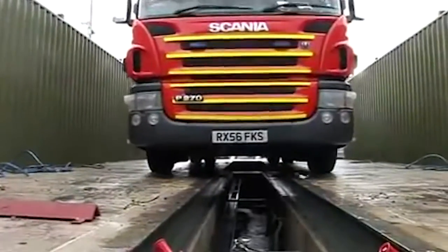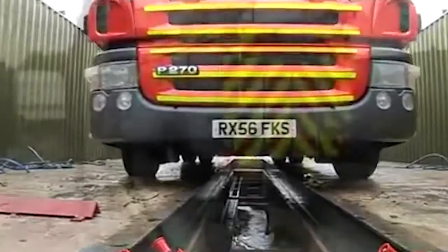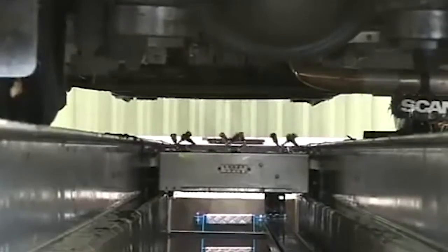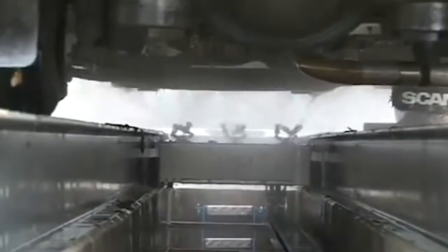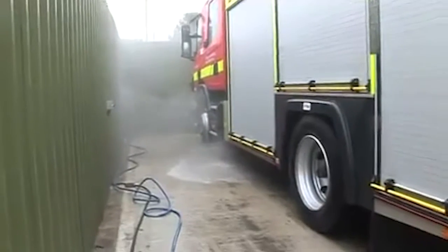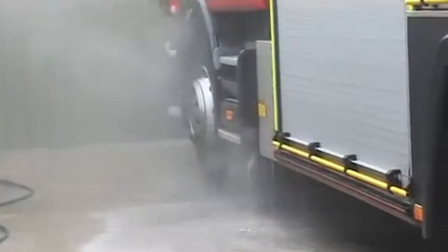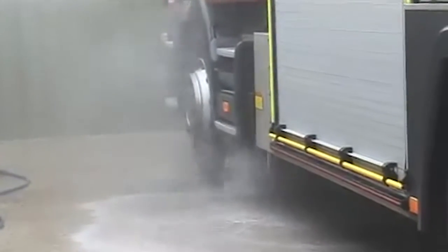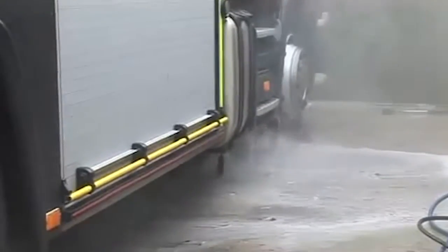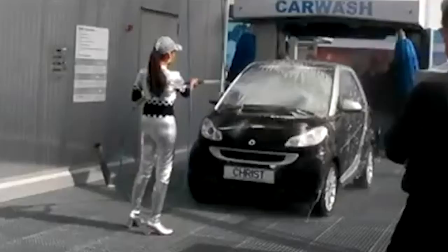The cost of clean water is spiralling, and its abundant supply is not guaranteed in the long term. There are two ways to reduce water usage. One is to increase the spray pressure to achieve the same cleaning effect but using less water. There are still companies that use low pressure, 5 to 10 bar, instead of 40 to 70 bar. The other is to use recycled water. It increasingly makes both economic and environmental sense to use recycled water. But therein lies a potential problem.